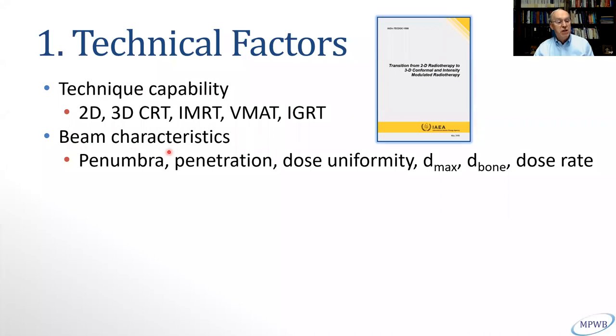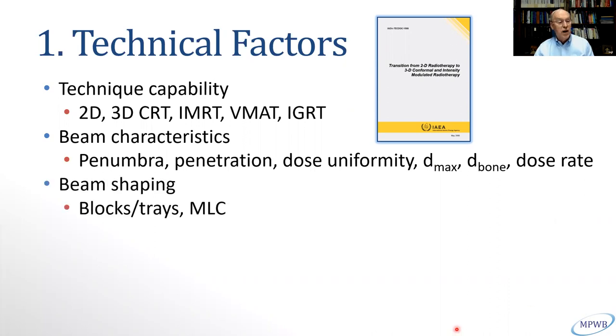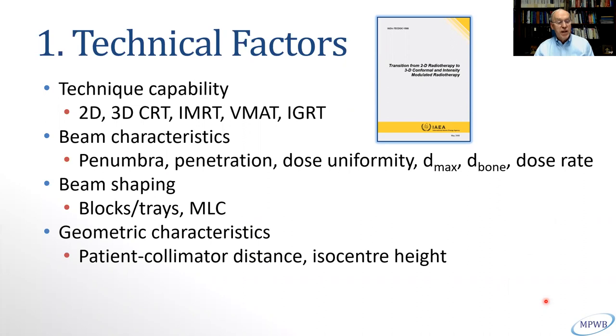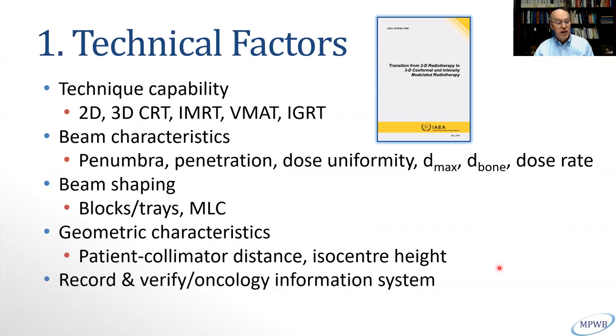Beam characteristics is often what's used to compare cobalt and linac and other technologies—penumbra, penetration capability, dose uniformity, depth of maximum dose, dose to bone, dose rate, and so on. Then there's beam shaping: do we use block trays or multi-leaf collimators or something else? Geometric characteristics: patient collimator distance, isocenter height. You'd be surprised how much variation there is in average height of people throughout the world, and the impact isocenter height has on that. And then we need to consider record and verify, the oncology information systems—the digital component of the technology.